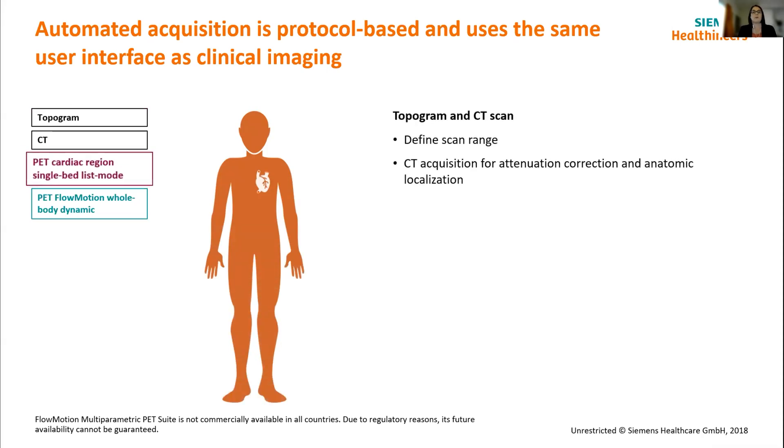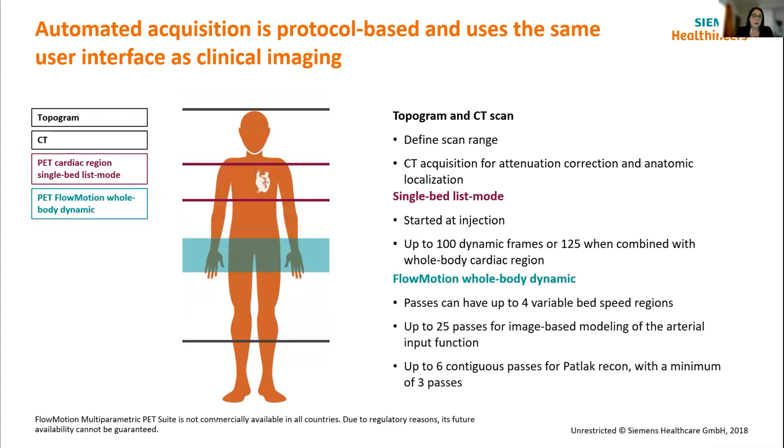One of the other exciting aspects coming for dynamic imaging is FlowMotion multiparametric PET. FlowMotion multi-parametric PET was initially designed for Patlak modeling — automated Patlak imaging using an image-based arterial input function. As mentioned, it's really nice not having to do the invasive side of the procedure and being able to do that image-based approach. The green line bobbing up and down in the image is indicating the bi-directional table motion of continuous imaging. With the Quadra, the green band would be much larger, opening up the realms of possibility for different dynamic passes.